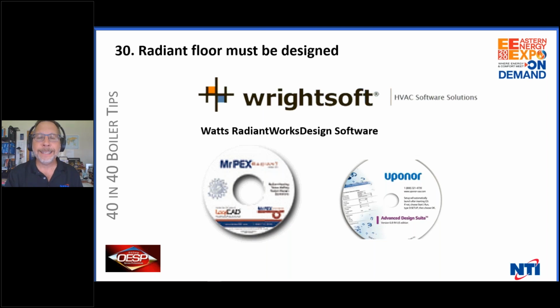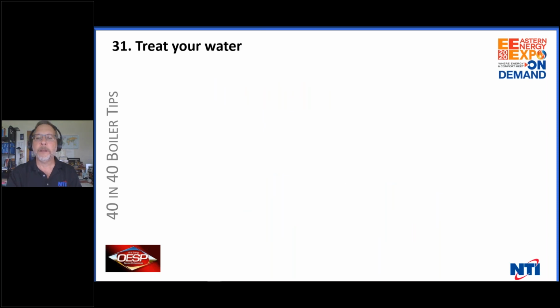Please size your systems, or have your manufacturer's rep or your manufacturer size and design your radiant. It's an integral part of the system. This isn't a $100 screw up. This is tens of thousands of dollars of screw up. Once the tubing's in the concrete or between the floors, you're not changing it. Please design it correctly. Treat your water.